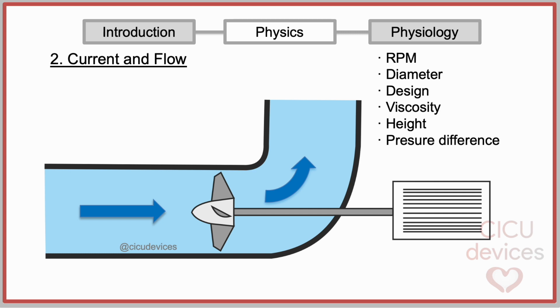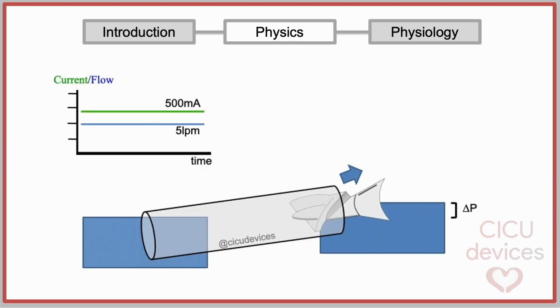Impella device is a microaxial pump, so the flow it generates follows the principles of such machines. Flow in axial pumps depends on various factors: rotation speed, impeller diameter, impeller design, fluid viscosity, height at which the liquid is being pumped, and, in the case of ventricular assist, the pressure difference between cavities. In this way, if the catheter and patient remain constant, we can consider that the obtained flow depends mainly on the pressure difference between the inlet and outlet.